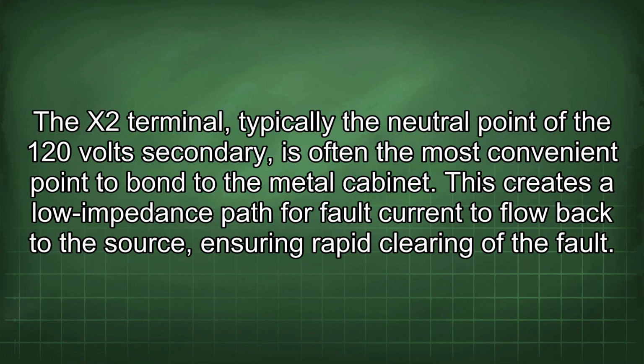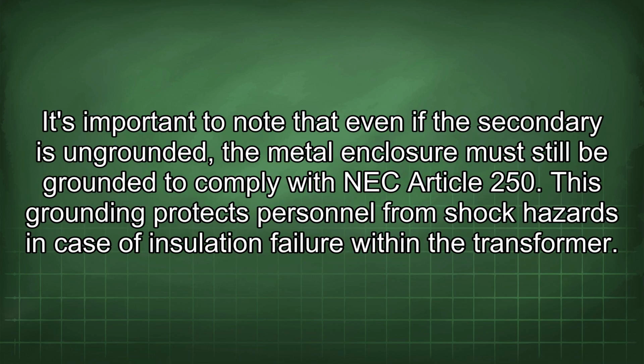The X2 terminal, typically the neutral point of the 120 volts secondary, is often the most convenient point to bond to the metal cabinet. This creates a low impedance path for fault current to flow back to the source, ensuring rapid clearing of the fault. It's important to note that even if the secondary is ungrounded, the metal enclosure must still be grounded to comply with NEC Article 250. This grounding protects personnel from shock hazards in case of insulation failure within the transformer.